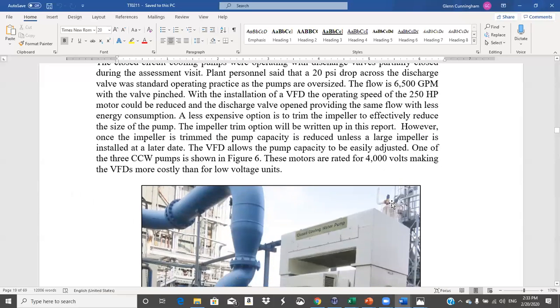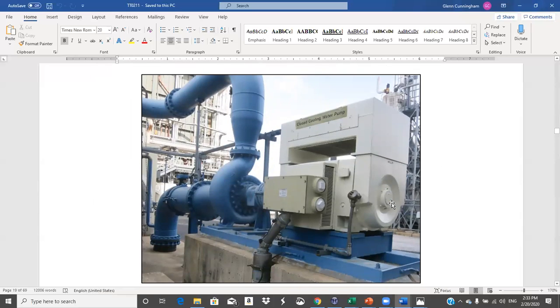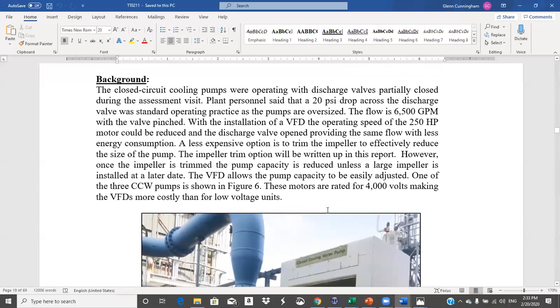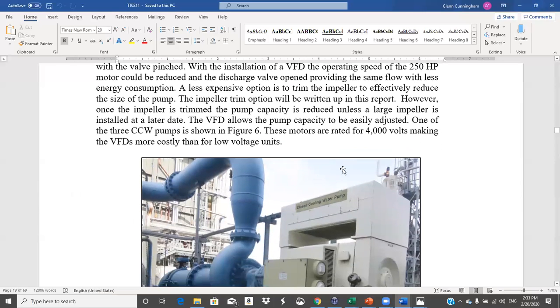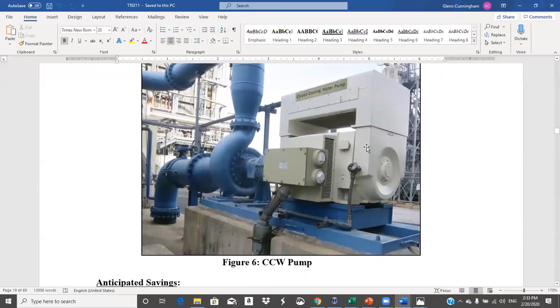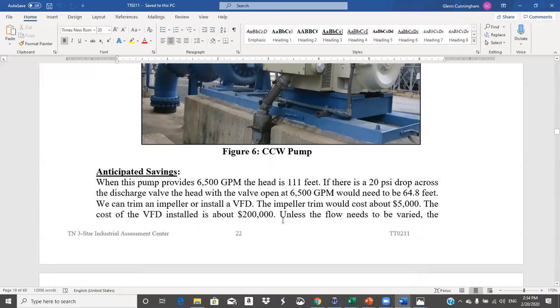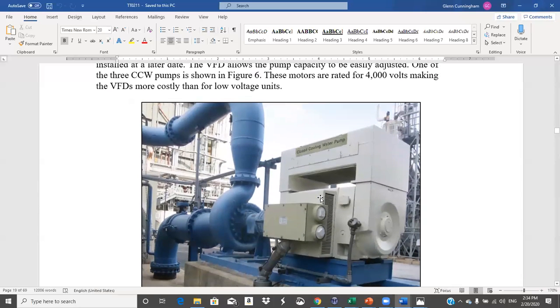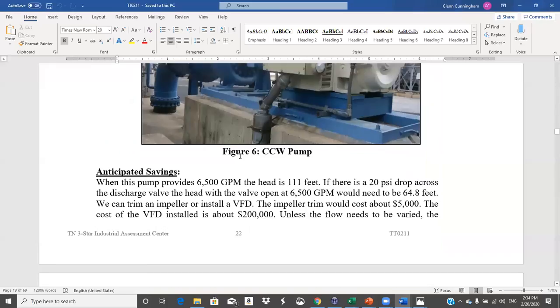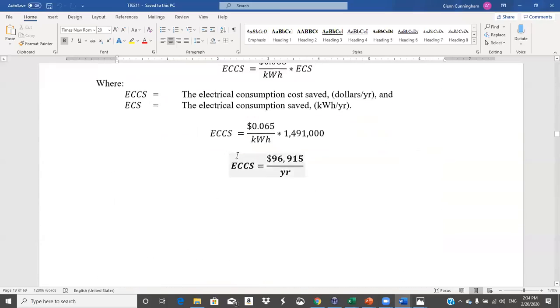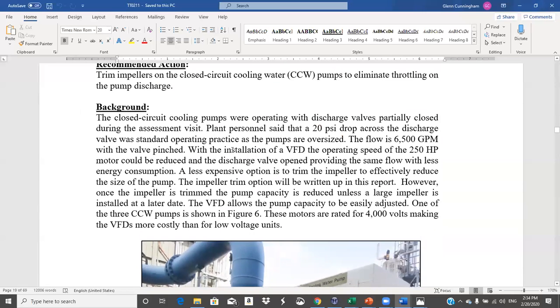Okay, trim impellers. This is their closed cooling water pump, and they had one of these per unit. What's the horsepower? I forget now. 250 horsepower motor, and it works at 4,000 volts. I don't know, did we do a VFD? VFD or impeller trim. If you don't want to adjust it, there's a valve around here someplace. This is the discharge line. The suction comes in the middle and then the discharge comes up, and it's a cooling pump. I think that's going to the condensers. I don't have a picture of the valve, but the valve was pretty heavily pinched.